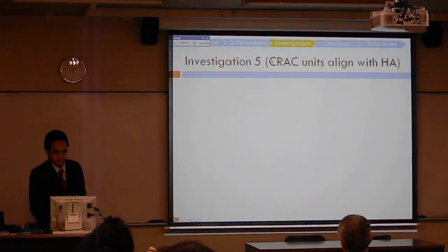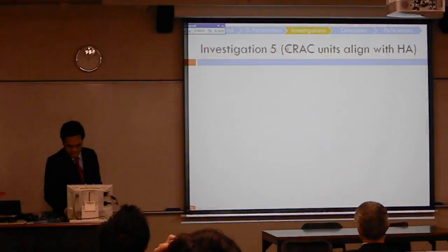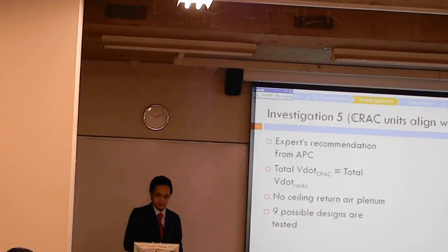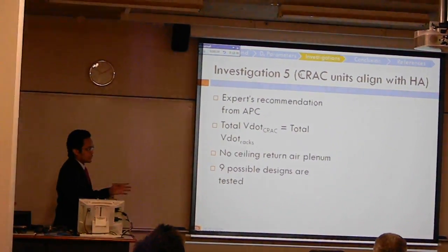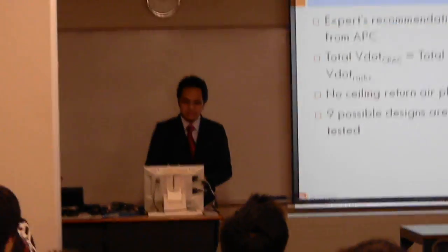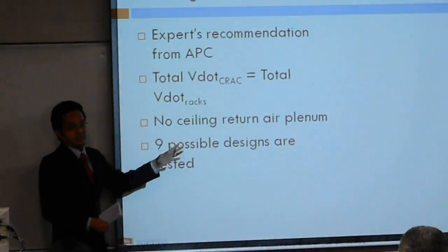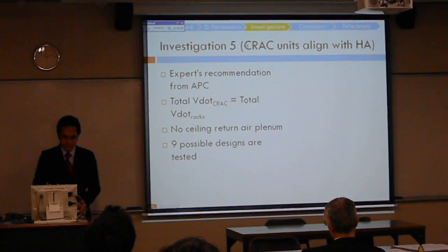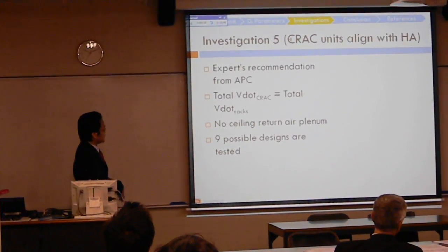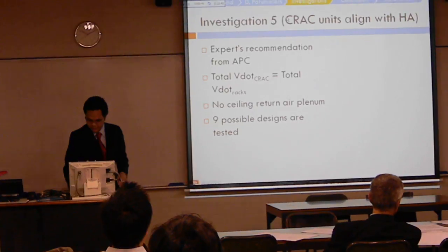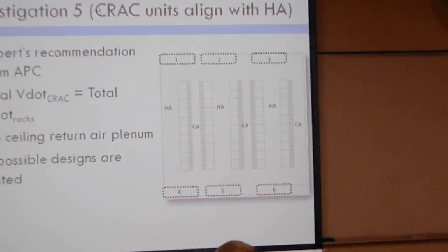This is Investigation 5, based on the reading I have made. A number of experts suggest that aligning the CRAC units with the hot aisle will effectively improve data center performance. Since this statement claims to give benefit, I reduced the total output of the CRAC units to be exactly equal to the heat dissipation — so this time there will be no extra airflow. And since the ceiling plenum is not beneficial, I removed that. Nine possible designs will be tested separately. These are the locations when CRAC units are aligned with the hot aisle.